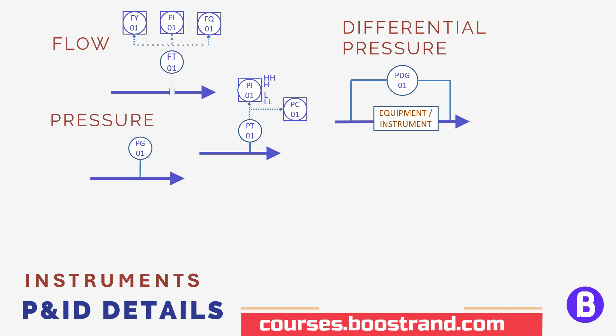We can also send the differential pressure reading to the control room and configure a high or a very high alarm, or even take a shutdown action. The same can be the case for temperature.